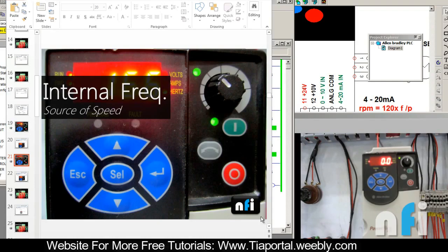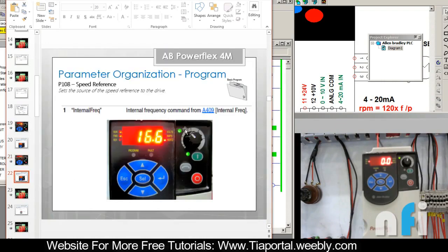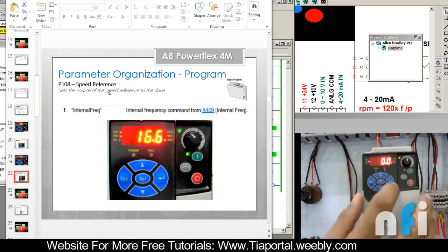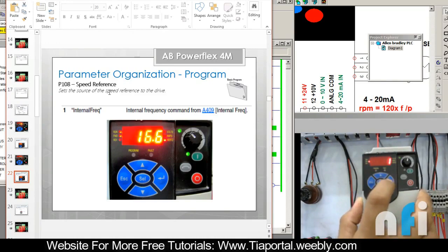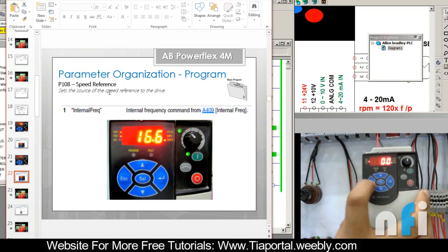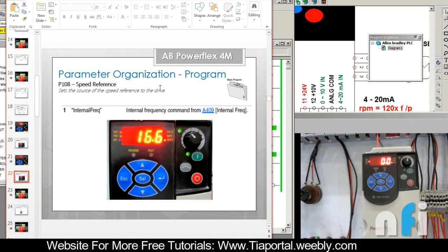Let's see what this frequency is and how we can set it. For the internal frequency, first we need to change the parameter of speed reference. By default it was 0, so we have to change that to 1 in P108. Let's do that step by step — this is P107, P108, put 1. Now go back. This is 0 as of now, so now we have to set the internal frequency.